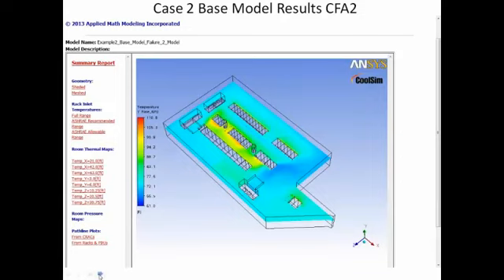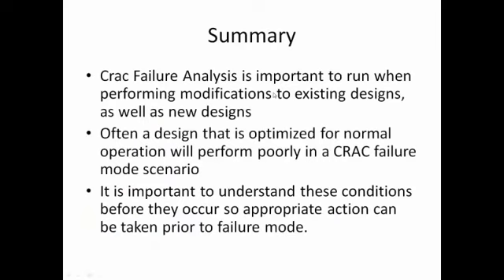Absolutely. Yeah. Absolutely. That would be important to any data center. Any data center. Whether you've got variable speed fans, fixed speed fans, whether you're turning CRACs off, whether you're doing failure analysis and trying to understand the failure condition, it's important to use a tool like this to understand exactly what those conditions are going to create for you as an environment prior to encountering them. It just happens to be we built this application to be able to do that more cost effectively than others, because you can run multiple jobs on this thing at the same time without penalty.